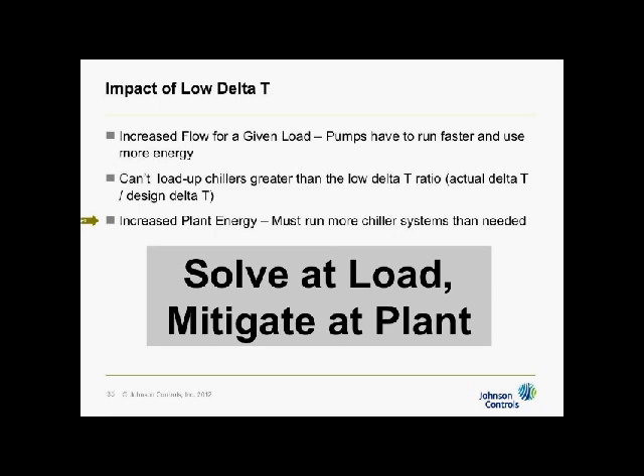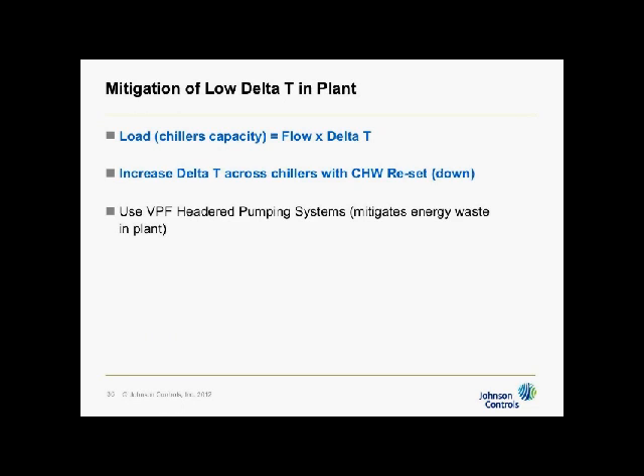You have to clean the coils, you have to recalibrate controls, replace leaky valves, etc. You cannot solve low delta T at the plant, but you can mitigate it. It's just very difficult to do so with primary-secondary. Okay? Remember, load is equal to flow times delta T. The only way to do any mitigation with any pumping system is either to increase the flow above design or increase the delta T back to design or above design.